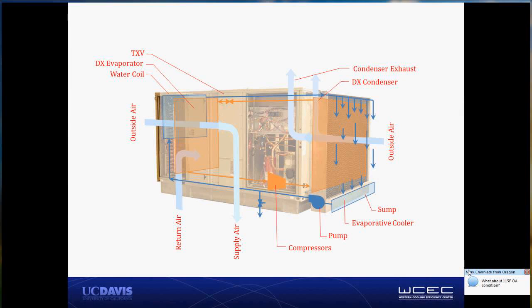For folks that aren't completely familiar with it, here's an overview diagram of how the dual cool works. You have a vapor compression circuit marked out here in orange with your condenser on the right-hand side, the evaporator coil on the left-hand side. Typically, that evaporator coil would be covering the cooling for a mixture of return air and outside air, and you'd be bringing outside air across the condenser coil. In this case, we're pre-cooling the condenser air as it comes in from outside with a direct evaporative media. The water from that system is cooled down very near to the wet bulb and is collected in a sump.